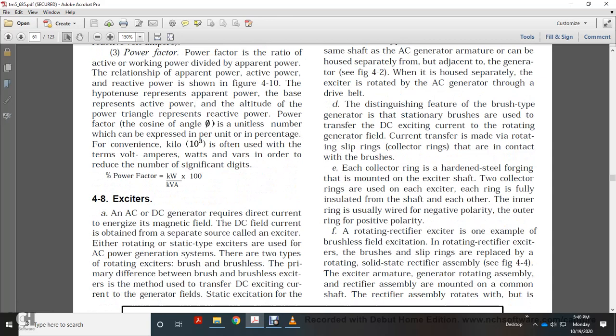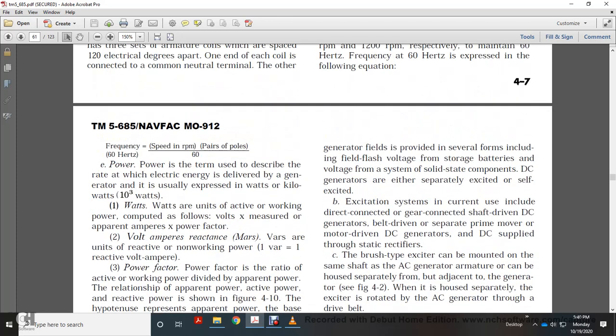All right, 4-8, exciters. An AC generator requires a direct current for the energy of the magnetic field. The DC field current is obtained from a separate source called the exciter, either rotating or static type. In AC power generation systems, there are two types of rotating exciter, brush and brushless. The primary difference between the brush and brushless exciter is the use of brushes for the transfer of the DC current to the generator field. Static excitation of the generator field is provided with several forms, including field flash, voltage storage battery, and solid state voltage systems.